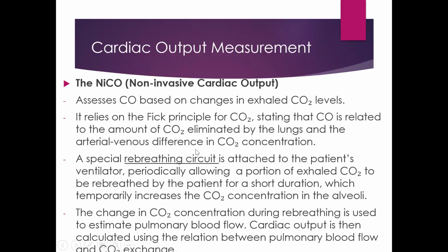The last one we're talking about is the NICO system. Instead of using oxygen consumption, the NICO system uses exhaled carbon dioxide. So the NICO system assesses cardiac output based on changes in exhaled carbon dioxide levels.